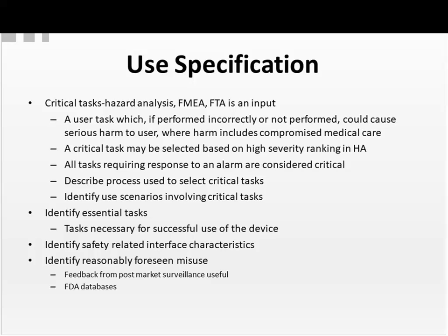We identify the safety-related interface characteristics and reasonably foreseen misuse. We brainstorm and think of how could the device be misused. And inputs to that are the FDA databases, recall databases, MDR databases, and feedback from post-market surveillance for similar devices.